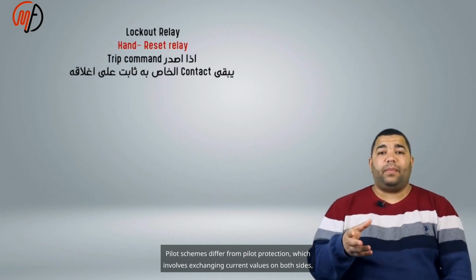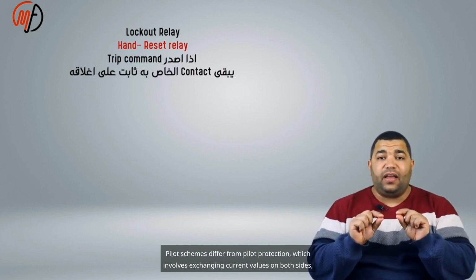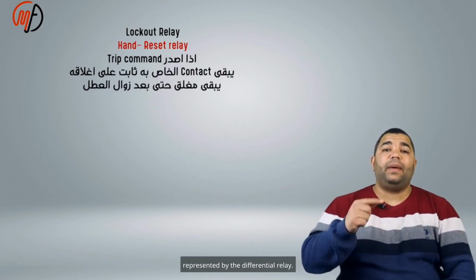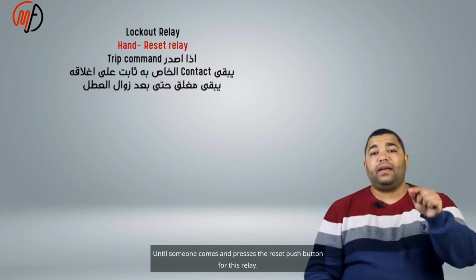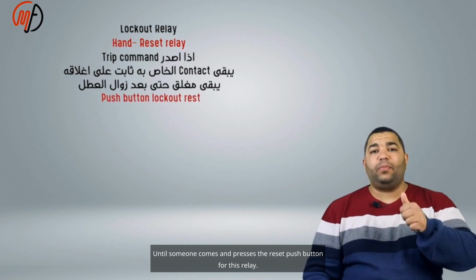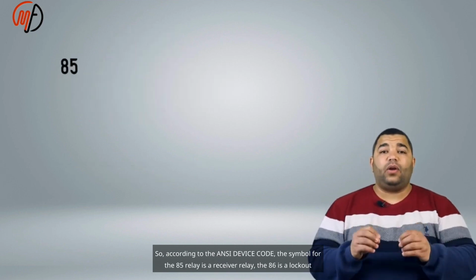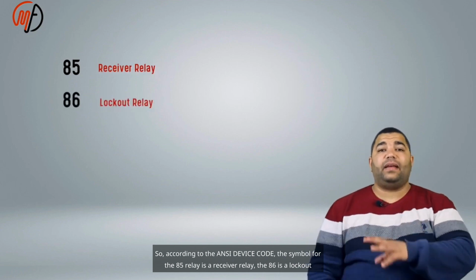Pilot schemes differ from pilot protection, which involves exchanging current values on both sides, represented by the differential relay. The lockout relay stays closed until someone comes and presses the reset push button for this relay. So according to the ANSI device code, the symbol for the 85 relay is a receiver relay.